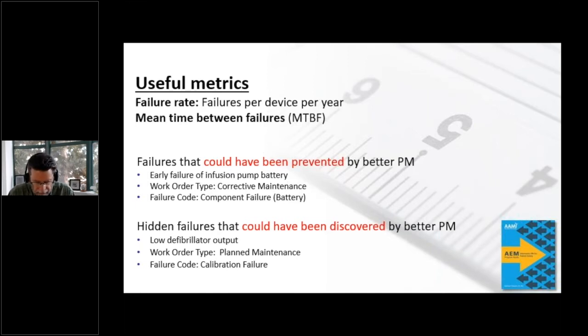The issue is that there are some failures that could have been prevented by better PM, and some that could have been discovered by better PM, as we were talking about. I had some examples on the previous slide, but you can already see material from earlier this morning about failure codes and different types of failures, and the fact that some of these are related to PM and some are not. For example, we had the example of misprogramming an infusion pump. You can do PM all day long and you're not going to solve that problem. You need to know about it, you need to do something about it, but the answer is not more PM. So distinguishing PM-related failures, as defined here on this screen, from other types of failures is an important part of what you could do with this information.